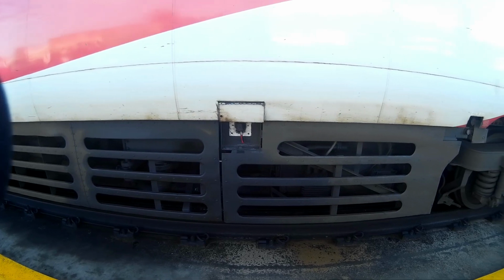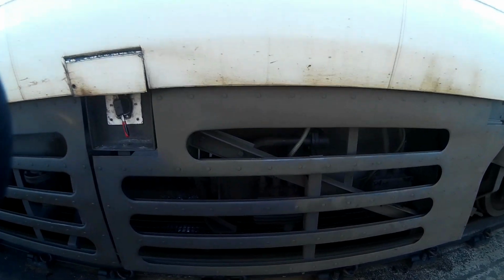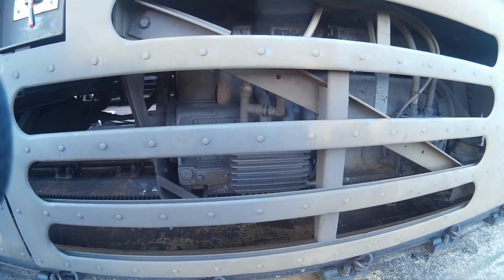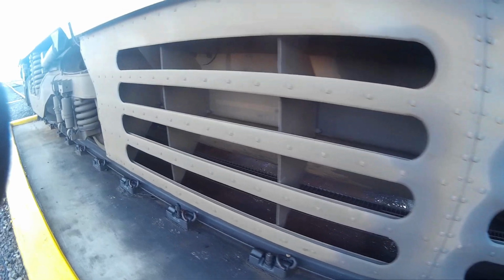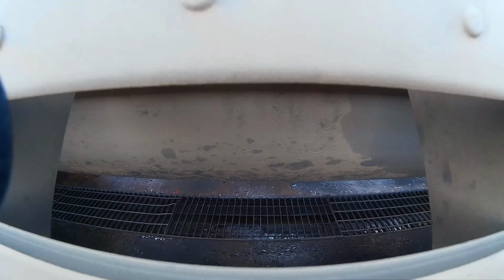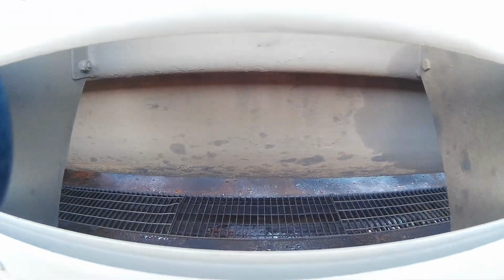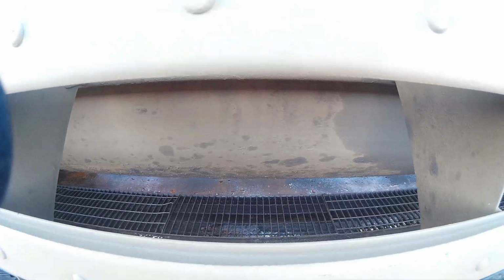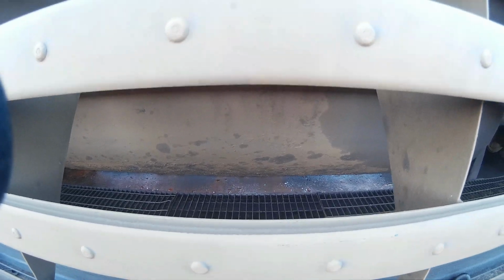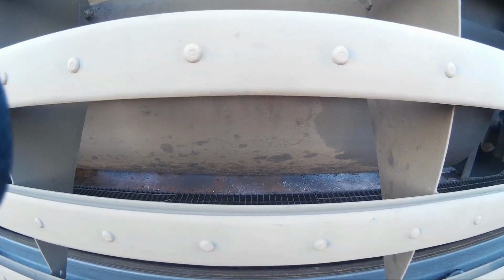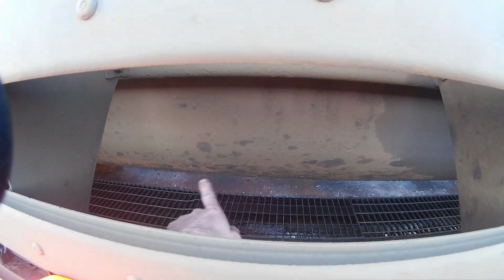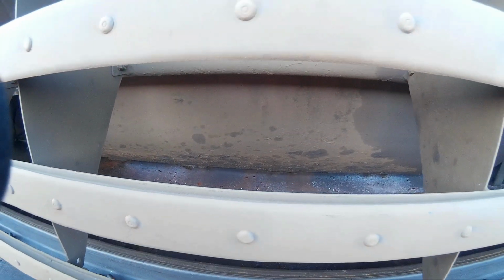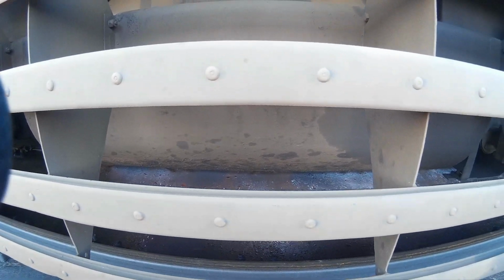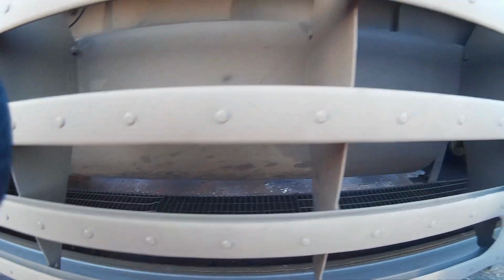Underneath the locomotive, between the bogie frames, we have our 2 air compressors at number 2 end and our transformer towards number 1 end. The transformer is underslung in 1500 litres of oil and kept cool by radiator blowers forcing air into the plenum, which is what we can see here, just the bottom of it. The rest of the transformer is inside, we can't see it.